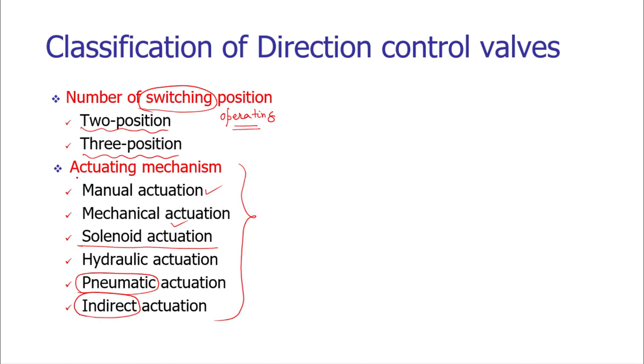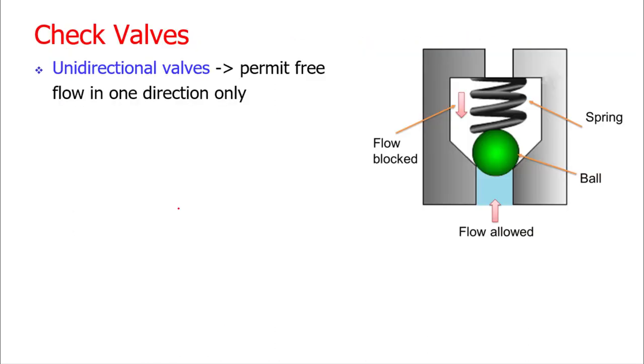Now let us study the first valve: the check valve. Check valves are unidirectional valves — they permit flow in only one direction. A typical check valve construction shows the valve body with a passage. Fluid enters at one opening and exits at another. Inside the valve, a space is machined or cast to house the construction elements. The basic construction element of a check valve is a spring — it is a spring-loaded ball valve using a ball to control the direction of fluid.